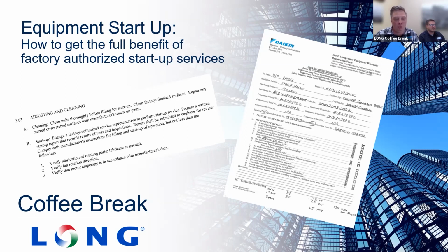This is the best time to make sure that the equipment is operating according to the specified control sequence and tune the machine with the cooperation of the controls contractor and the TAB contractor. And then fast forward to the startup result, we want a properly operating piece of equipment, and the startup date is often associated with forms that are used to begin the clock on the warranty date. But in between the requirement and warranty period, there are some important activities that need to take place, and that's where Rick is going to talk about some of these activities and some of the issues to avoid so that we can get the most out of the technician's time on site.